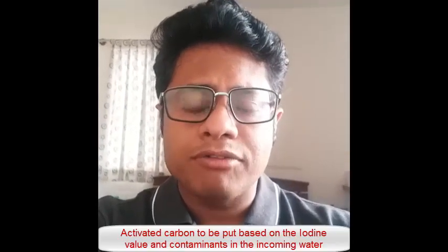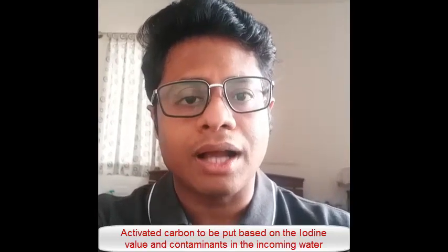What is an activated carbon filter used for? It is used to reduce total organic contaminants, TOCs. If there is a little smell because of organic contamination, the smell will go away and the color will go away. Apart from this, any chlorination done in pre-filtration will get removed by the carbon filter. When you replace the media for a carbon filter, you should know that the carbon used is specific to your water quality. For example, carbon is graded based on iodine value. Some carbon is impregnated with special materials to remove special contaminants from your water.